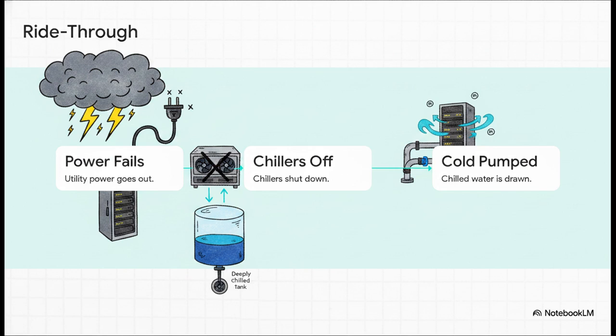Instantly, the massive mechanical chillers, the machines that actively cool the facility's water, shut down. Now, even with backup generators kicking in, chillers can take several agonizing minutes to reboot, stabilize, and restart their compressors. In the data center industry, surviving these blind spot minutes is absolutely crucial, and it's called the ride-through.